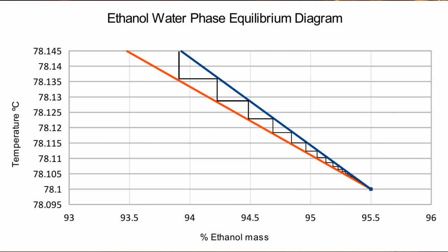You can see from this expanded bottom right corner of the water alcohol phase diagram that the difference in temperature between the top stages of an azeotropic distillation column is extremely small, thousandths of a degree centigrade. It varies with atmospheric pressure by much more than that, and any scheme to measure temperature so accurately is prone to errors that will also dwarf these small differences. Thermometric equipment that allows temperature resolutions down to a thousandth of a degree is extremely expensive, and for all these reasons column top temperature is not a useful control parameter.